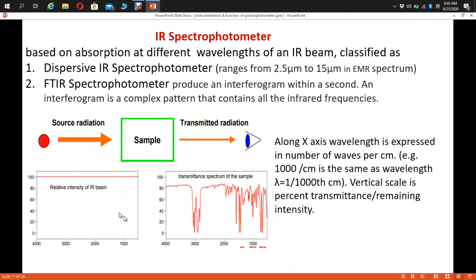In single beam instruments, instability due to lack of compensation for disturbances like electronic circuit fluctuation, voltage fluctuation, mechanical component instability, or drift in the energy of the light source makes abnormal fluctuation in the results. While in the case of the double beam spectrophotometer, because the sample beam and the reference beam pass at a time, these mechanical component instabilities, electronic fluctuations and voltage fluctuations are minimized. And as we have already discussed, little or no lamp warm up time is required, which not only improves the throughput of the result but also conserves the lamp life. As a result, the results obtained by the double beam spectrophotometer are reproducible, while single beam spectrophotometer results are less reproducible.